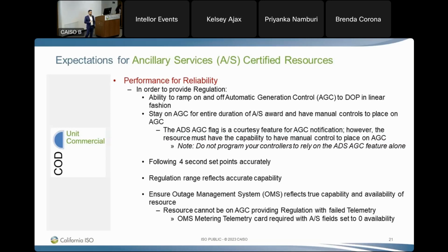Over the years, all our thermal sites were able to do this. If they had a problem committing on AGC automatically, we'd give them a call and they would manually switch themselves over to AGC. We call some of the battery sites and they say, all our controls are automatic, we don't know how to do that. Then you can't provide the regulation you were just awarded, and therefore we need to buy that back because you're not able to place yourself on AGC. So you have to have a way to manually place your unit on AGC. It's a must. You've got to have manual control because automation is great and nice, but when you need a backup, you've got to have that manual control.